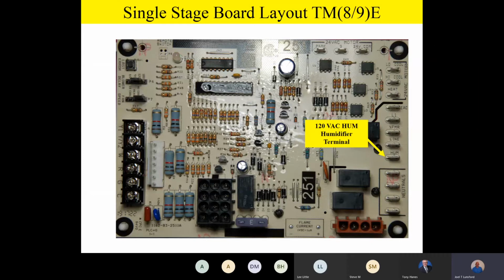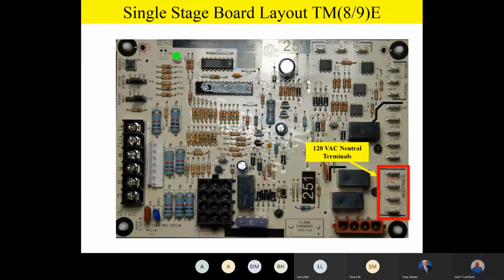Below those high voltage terminals, we've got 4 neutral terminals. And by the way, all those neutral terminals are bussed together. If you were to take that board and turn it around backwards, you'll see they're all tied together. And those are your neutral terminals. That's where your white wires for your 120 volt components are going.